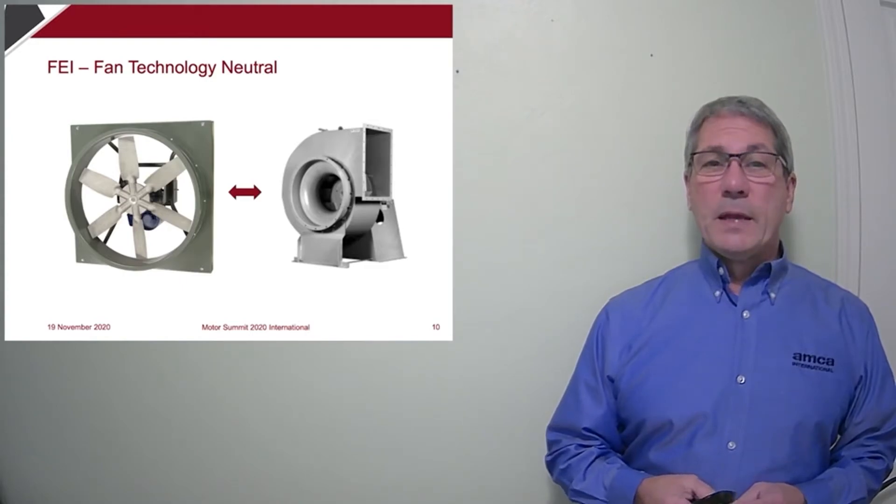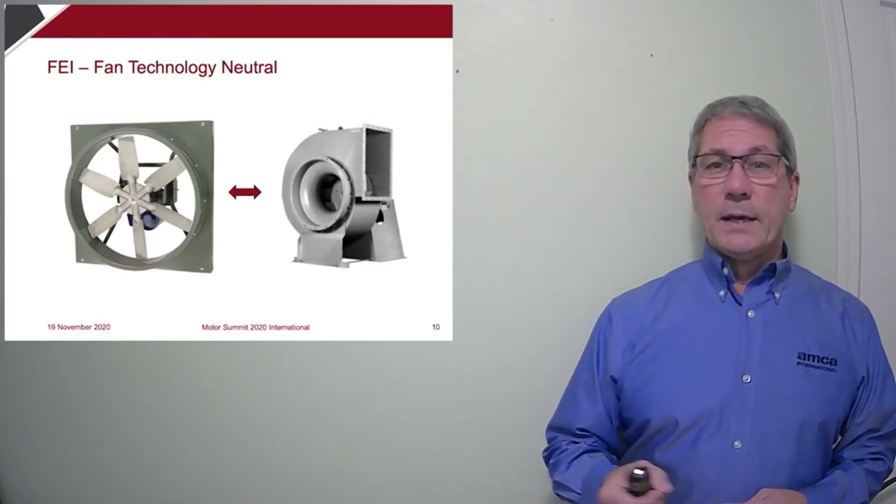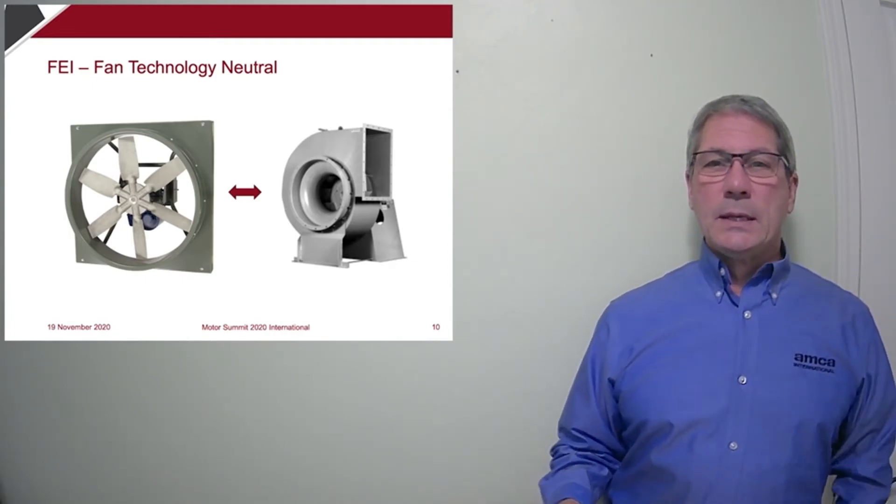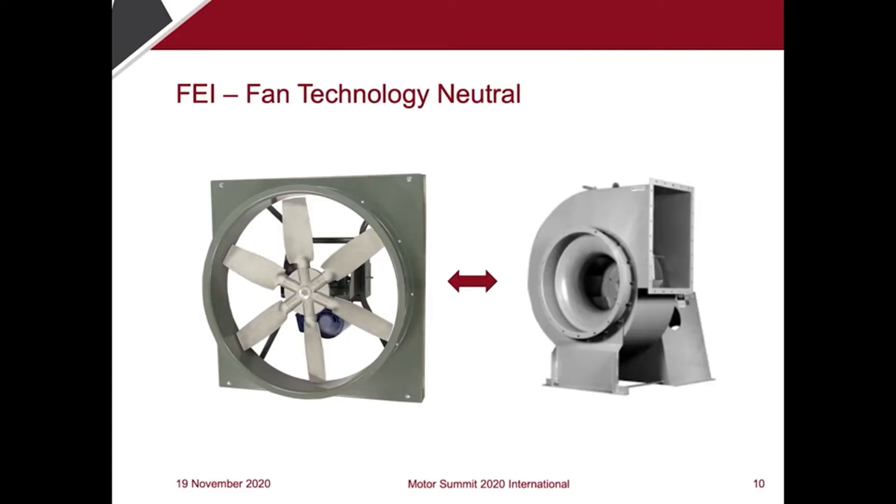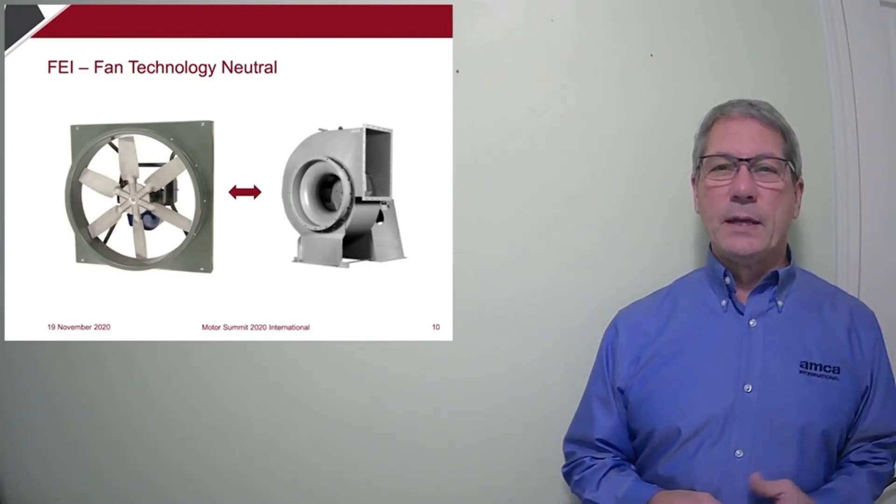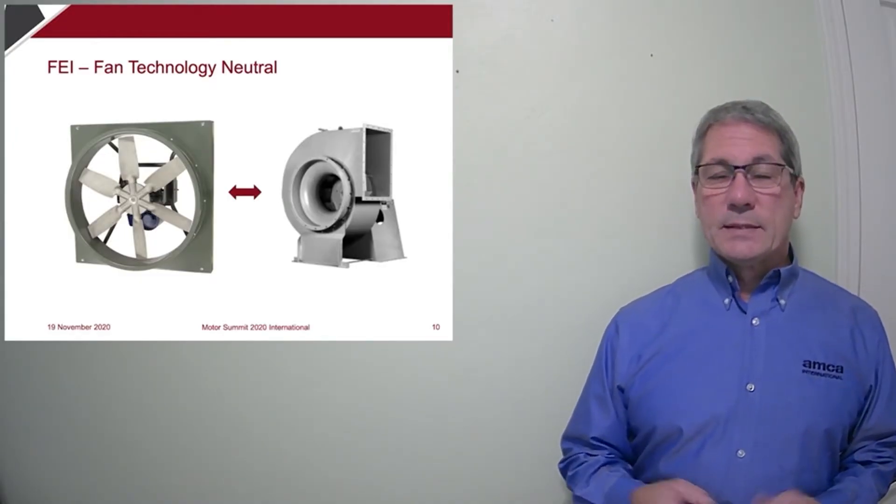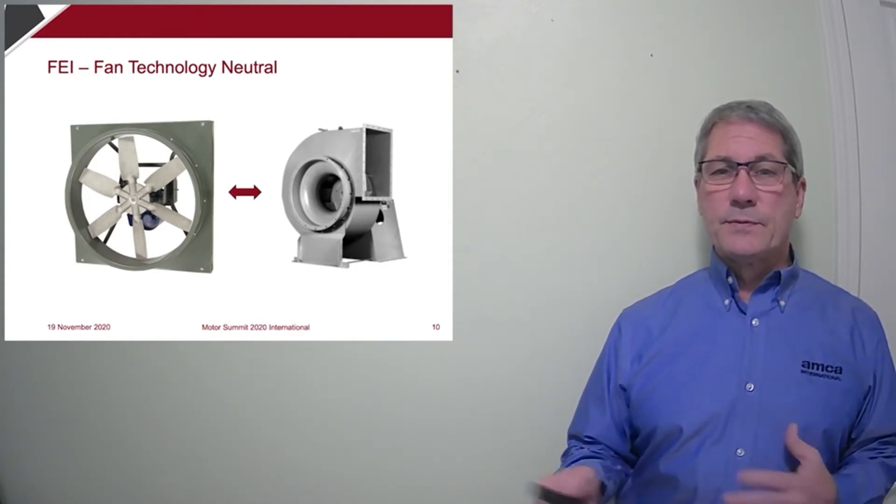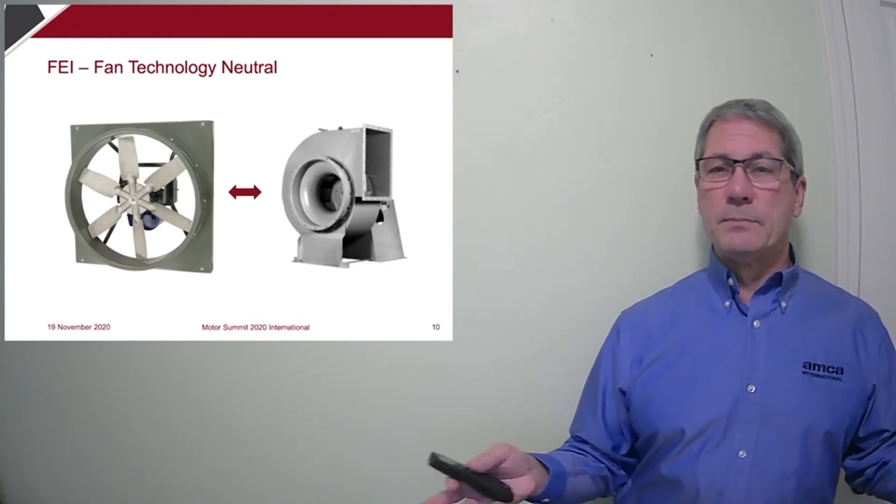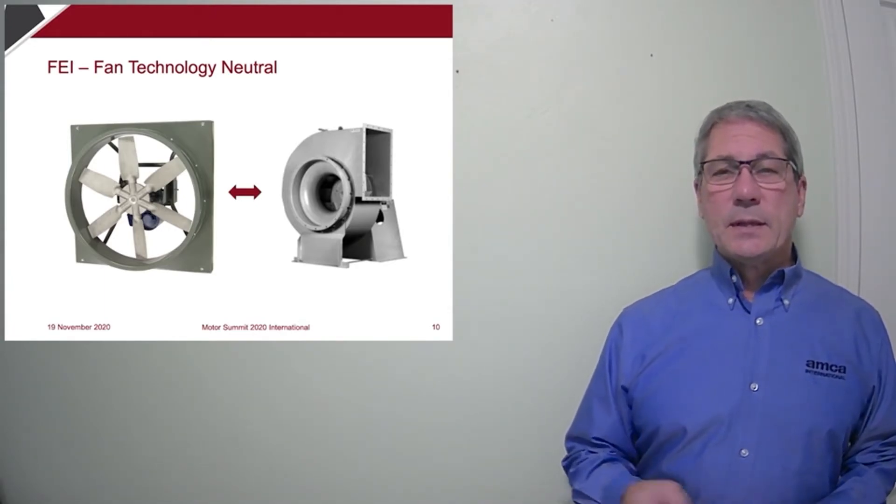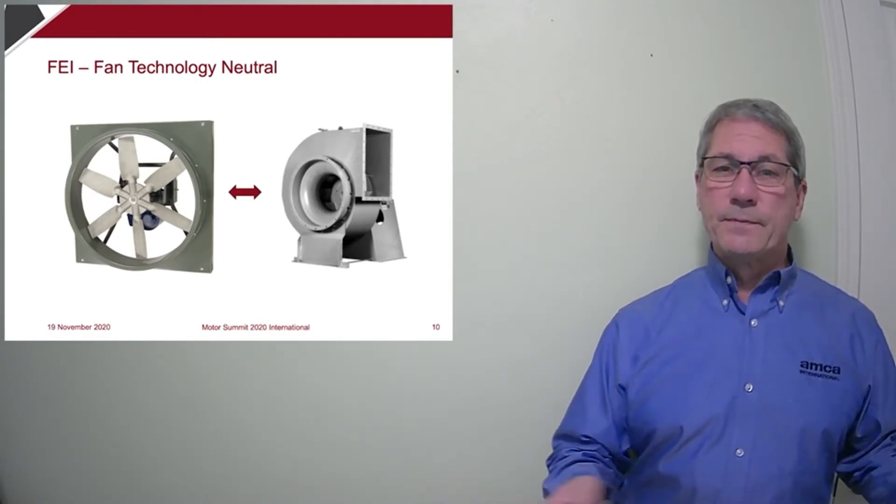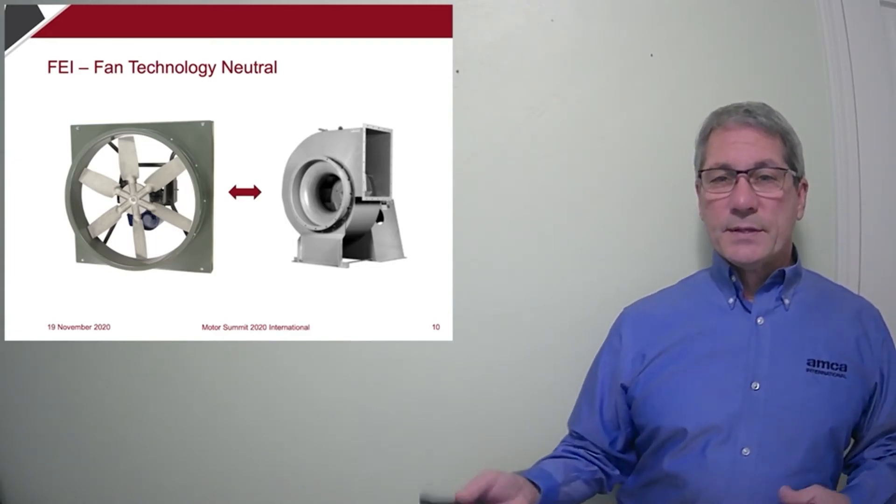Fan manufacturers were involved in developing FEI. And AMCA is all about leveling the playing field for fan manufacturers. So one of the main goals for FEI was to be technology neutral. We didn't want the metric to give any technology an advantage over another. This concept applied first to fan types. The same metric is used for all fan types from a low power prop fan to an airfoil centrifugal fan. So this enables and even encourages the use of more efficient fan types for a given application. The substitution.